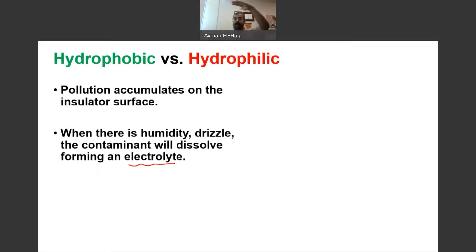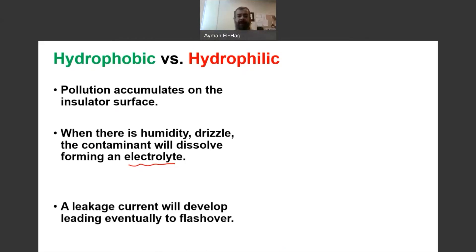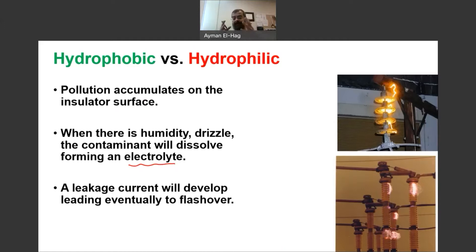Now, imagine a high voltage insulator energized from one end, grounded at the other, and an electrolyte on the surface. This is a perfect environment for a leakage current to happen on the surface. This leakage current can evolve into a complete flashover, which will cause interruption to the power system or can cause severe damage to the insulators.